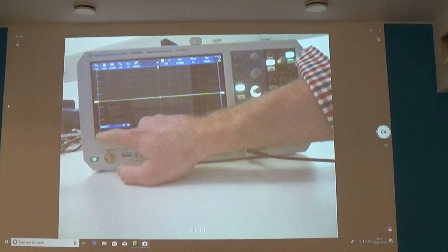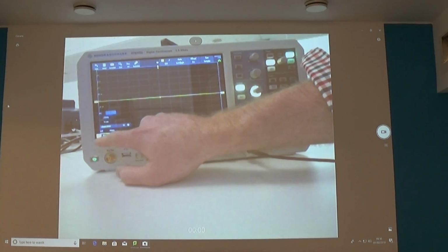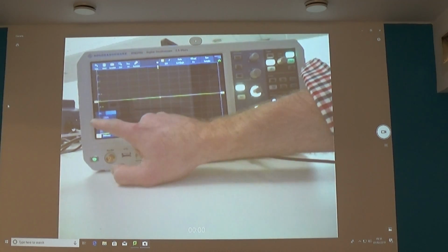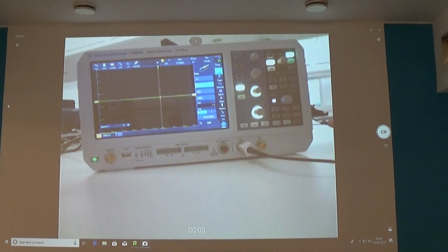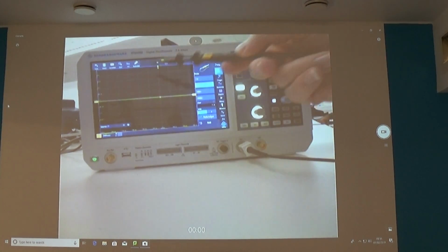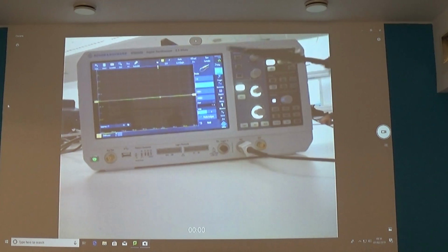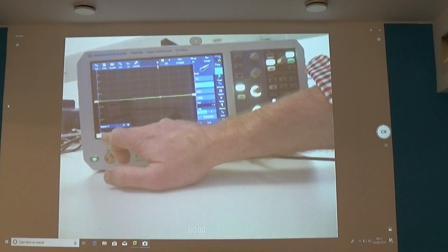So we can check channel 1. If we click down here, and we can say probe, we can see that the probe is set to 10 to 1. What that means is my probe tip is now matched to the input of the oscilloscope. So if I measure 5 volts on the tip of this probe, it's going to be showing me the correct 5 volts there. If I didn't have that, then my reading is going to be off by a factor of 10. Okay, so that's just the initial setup stage.